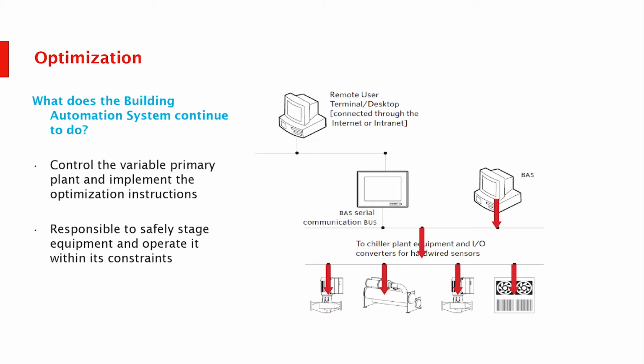So optimization is really about making decisions that make sense at that time based on the unique parameters that you're experiencing. Whether that be a change in the load, or a change in the specific efficiency of individual equipment, it's about working with the BAS to make better decisions. So the BAS continues to control the variable primary side. It continues to sequence the chillers. The chillers will sequence themselves based on speed, so you can see how many chillers to run. And then the chillers will ramp themselves up or down inside their technology, and run themselves with the embedded technology to make sure that they stay inside their safety zone, so they don't stray outside of their desired set point.